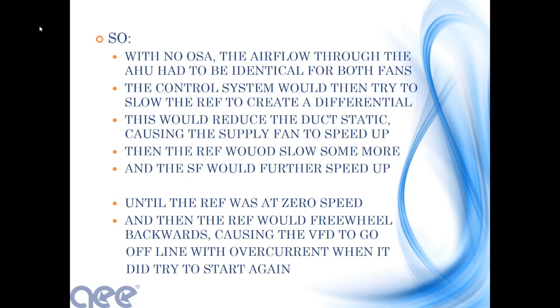Curiously enough, when we were running at full airflow, we actually had to run the return fan a little faster than the supply fan in order to have the building be at about 0.02 inches of water static pressure. Now stop and think about that. 0.02 inches. That's a shallow puddle of water on a tabletop. That's hardly any pressure at all. When we went to our low flow operation though, it was curious. We actually ended up slowing the return fan down and making it run slower than the supply fan in order to maintain our 0.02.